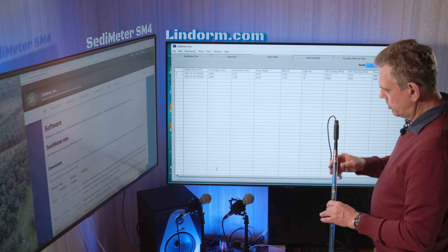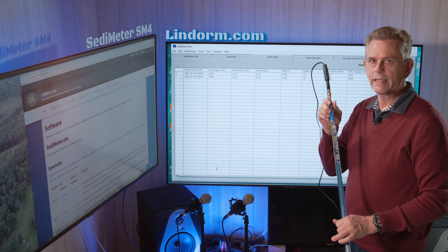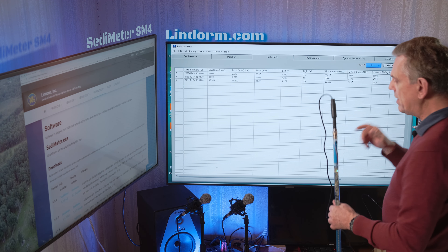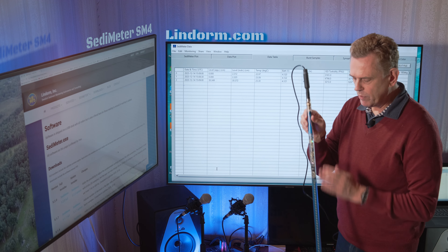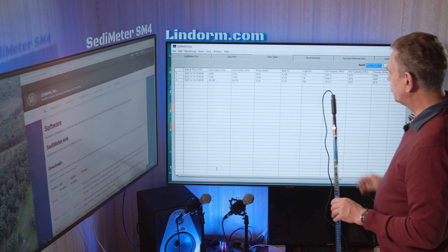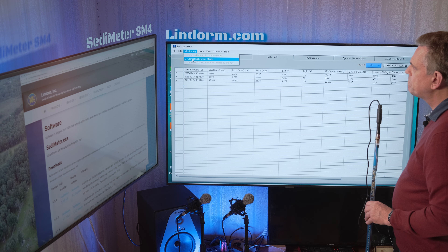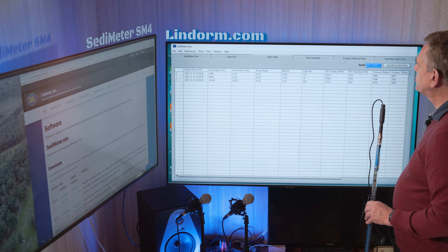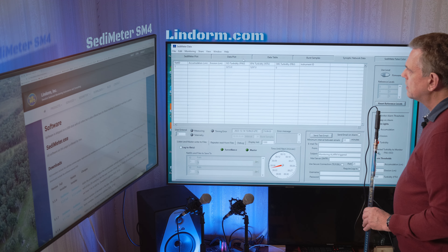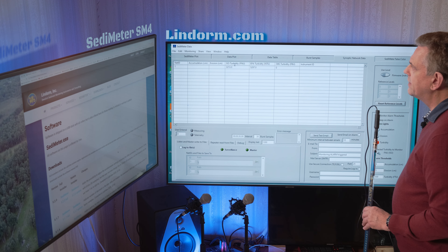If we get a conditions-based monitoring data point, it will have a different random second at the end. Since we are now in slave mode — the instrument controlled by the computer — it will not do conditions-based monitoring. If we want to test that, we have to stop monitoring and wait for the last measurement to be taken before closing this window.